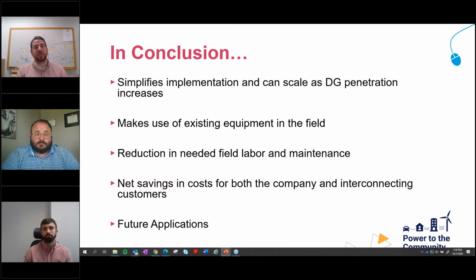A big thing my teammate Ryan's been involved with is trying to maximize the use and efficiency of switch capacitor banks going in with some of the DER sites. Some of the recent DER sites are not operating at unity - they have to operate off unity to mitigate other issues with their installation. So when they go in, they have to purchase a switch capacitor bank, and the switch capacitor bank isn't necessarily in a place where it sees their load and will see their generation. So you can't just operate it on VAR flow or load or voltage and get it to follow them.